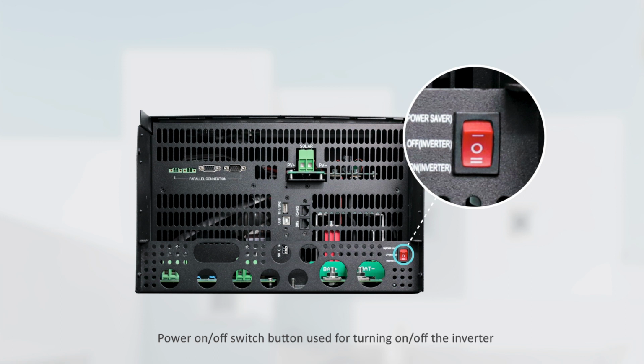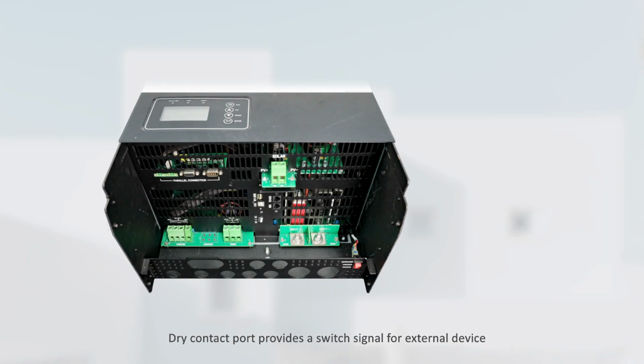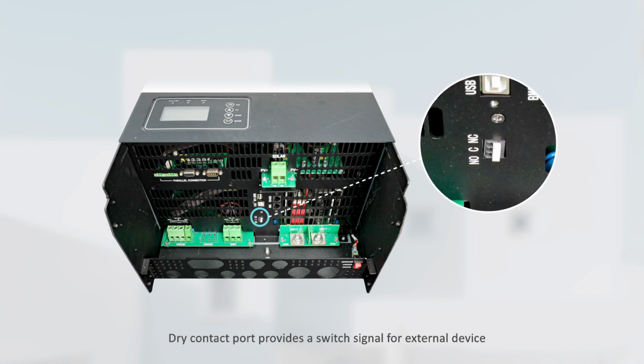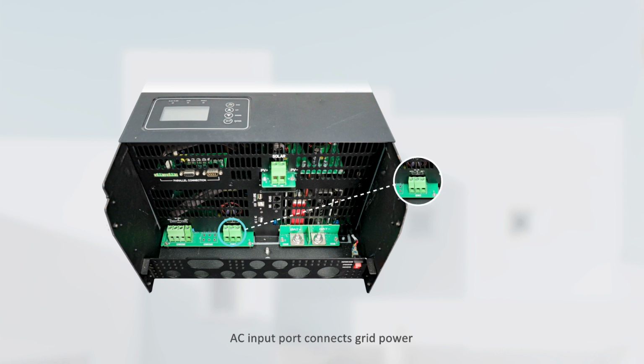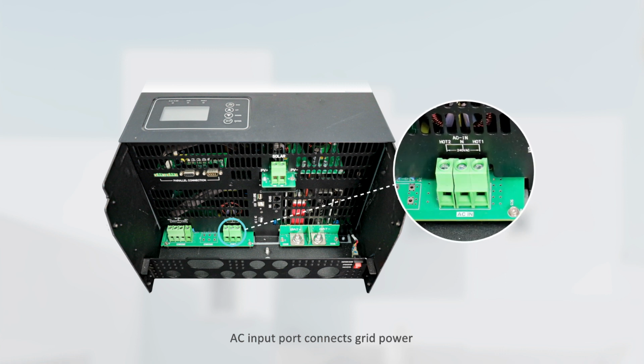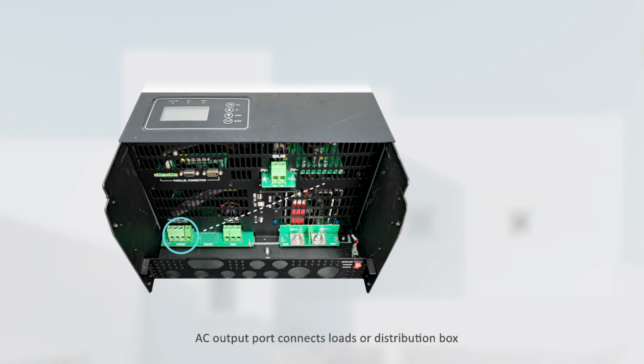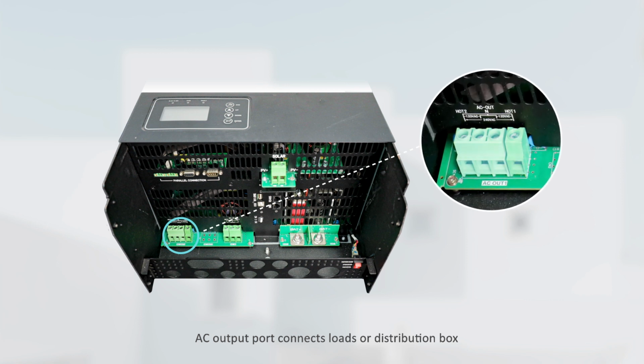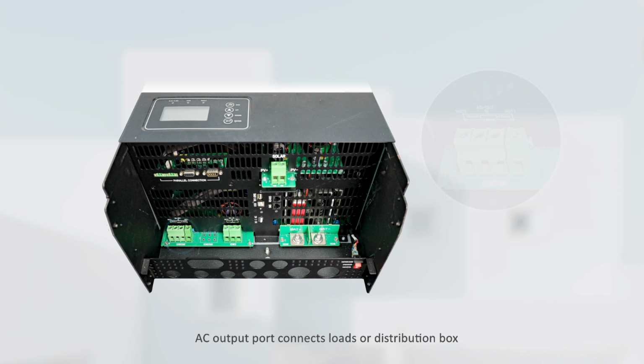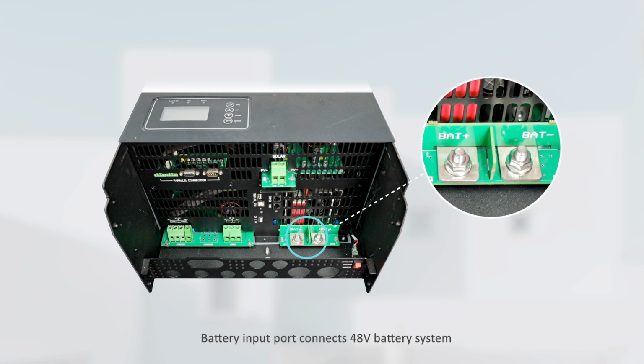The power on and off switch button is used for turning the inverter on and off. The dry contact port provides a switch signal for external devices. The AC input port connects grid power. The AC output port connects loads or a distribution box. The battery input port connects the 48 volt battery system.